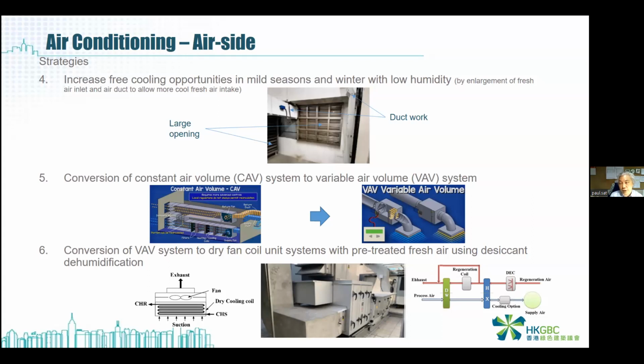Okay, and for those internal loads, such as the equipment load, lighting load, and also the sensible load of the occupants, they will use fan coil units. One of the benefits of doing it this way is that they can increase the supply chilled water temperature of the fan coil unit, so the compression requirements of the chillers can be less and become more efficient. Okay, so they can use this kind of thing.